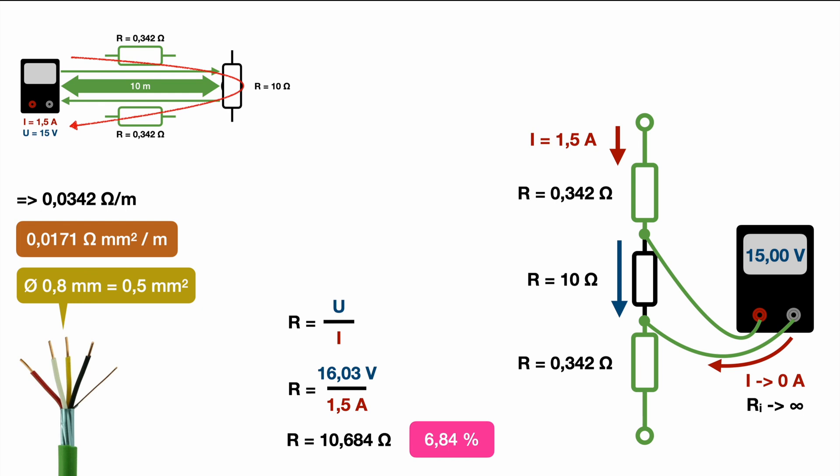We need this defined 1.5 amp measurement current to be able to calculate towards the resistance. But in case we use two wires to supply the resistor with this measurement current of 1.5 amps and we use two more wires to measure the voltage, we don't have any current flowing through those additional measurement lines we're using to measure the voltage drop. And that's the whole clue about the difference. That's the whole clue why the four wire technique is so much more precise.